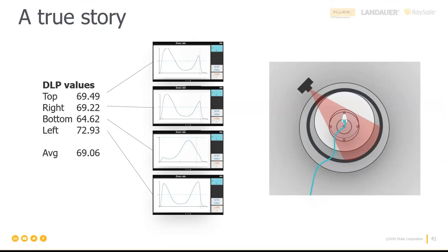So in this case, you would recommend going for the one that says bottom, which has the lowest reading? We measured in the four positions, and I took this as an example. The bottom one is the one I would save, but I would take three new exposures, one at the top, one at the right and one at the left. And I would only save them when I have one peak in the waveform. Correct. Because I still want to make four measurements.